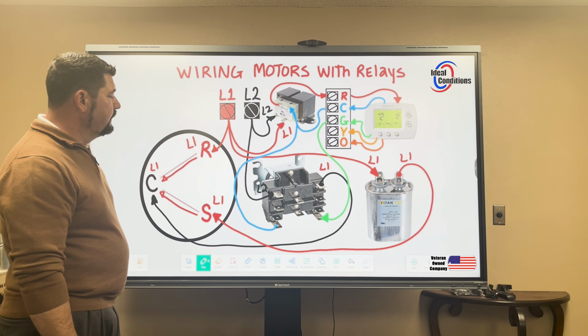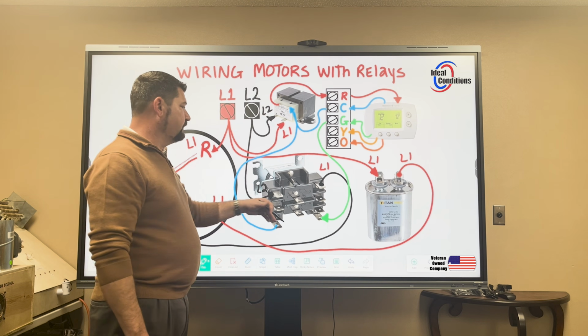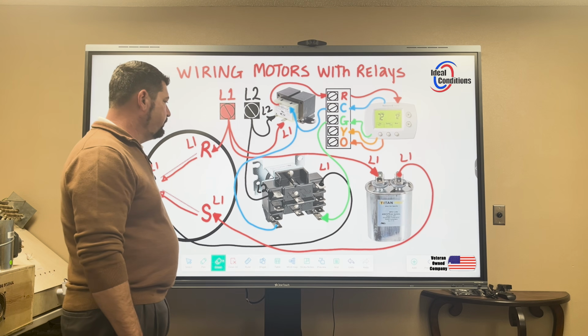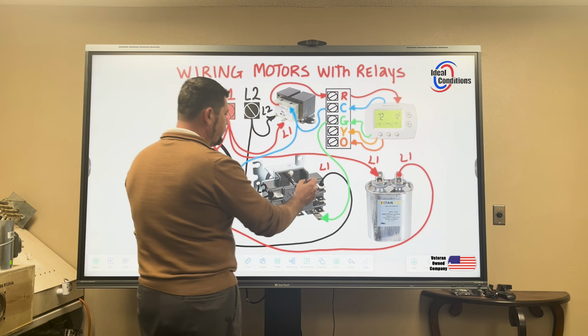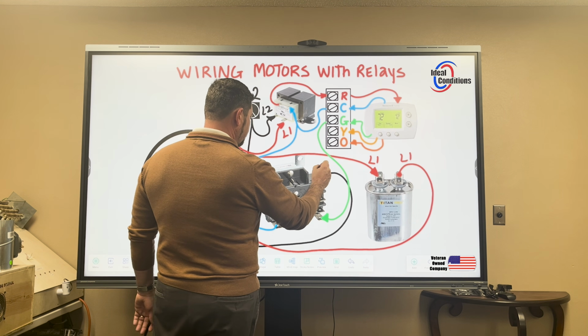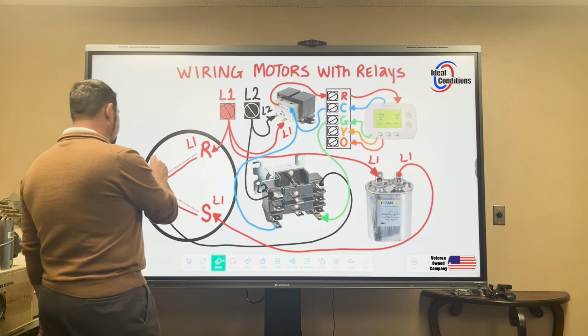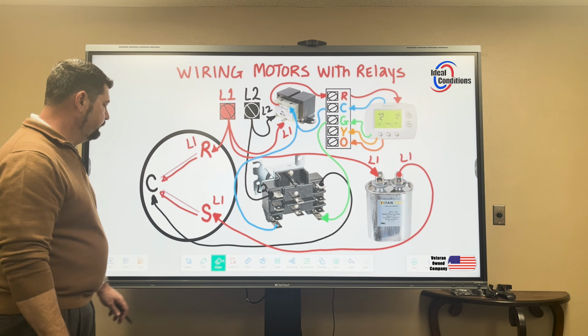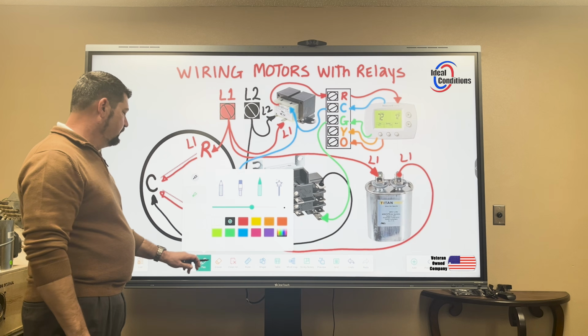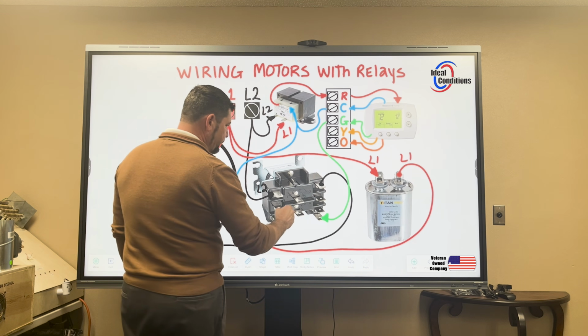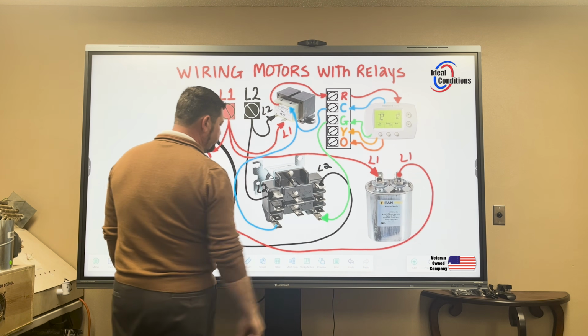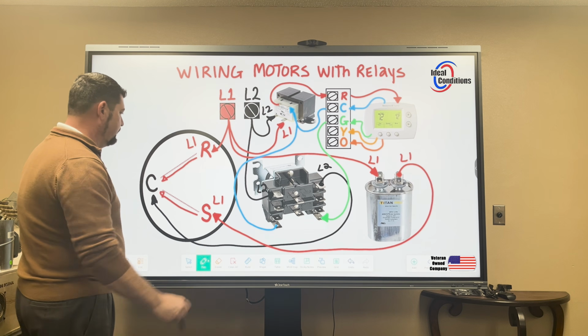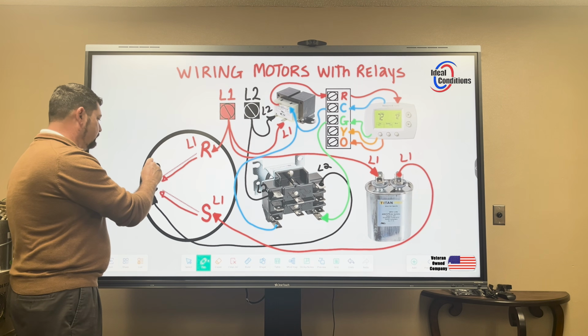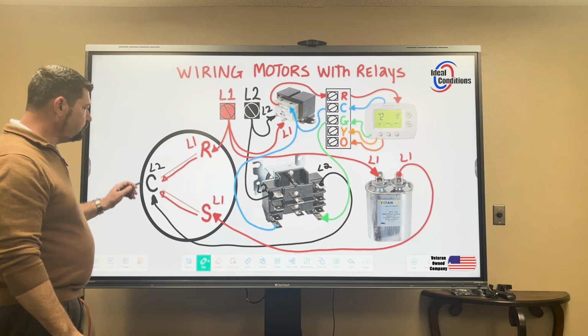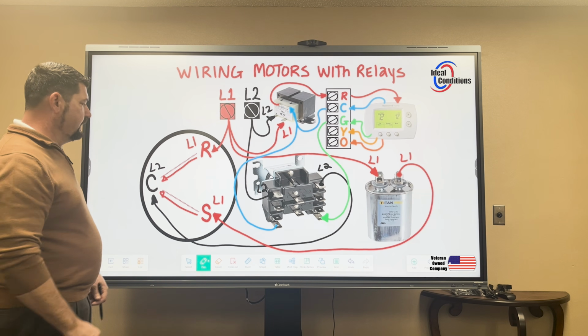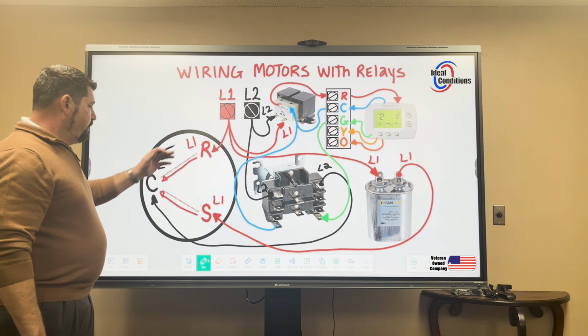There's nothing else here to wire up on the low voltage side, but we need to change a couple of things. The moment we got 24 volts here, there's no longer L1 present here or here. The moment we put 24 volts here on this relay, we now have L2 present, and because of that, L2 is now present here on our common terminal of our motor. At that point, both legs are present.